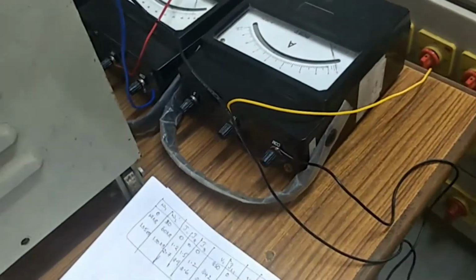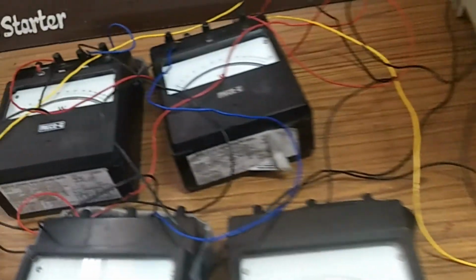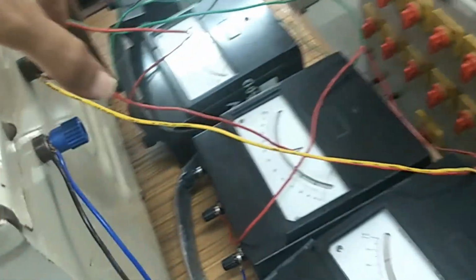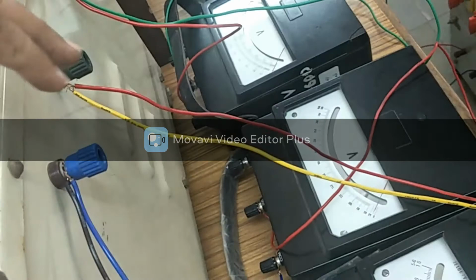You may get a doubt. As I said in the beginning, the three-phase supply is converted to two-phase. I have shown already, on the primary side you are going to have three-phase, but on the secondary side you can see here we have two single-phase loads. So this is one single phase and this is one single phase. So like that you are going to convert the three-phase to two-phase conversion of power. This is about Scott connection of transformers.